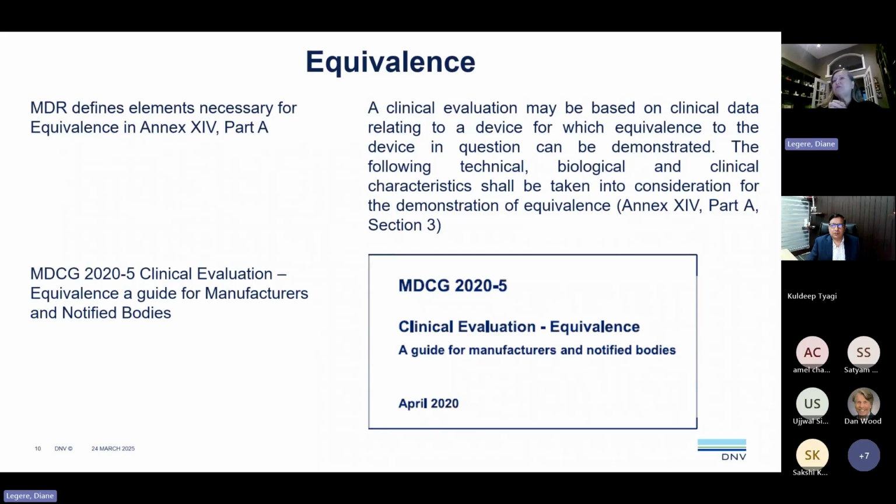But I will tell you, as a reviewer, when you show up with your technical documentation and this is confused, it puts a little shade on your understanding, or my assumption of your understanding, of the MDR. It feels like sometimes you've taken your FDA application and just sort of applied it and didn't take the time to understand the MDR, appreciating it's big, complex, changing.